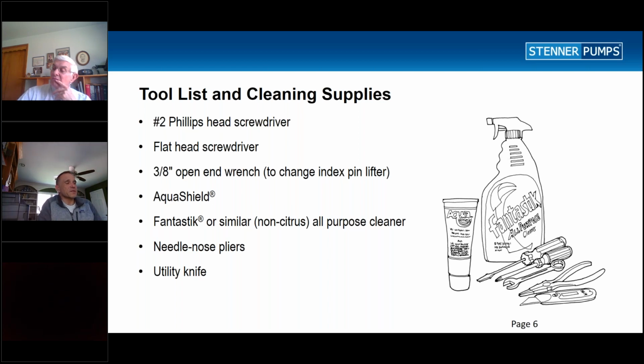One thing that I recommend is that anytime you do have a tube leak, because I see this happen often, we recommend taking all of the parts out of the head, taking the roller, shaft, take the housing off, and clean everything with some good clean water. And then also clean it with some Fantastik, and especially the rollers. One of the most likely things that happens when you have stuck rollers is when the chlorine starts getting crusty, it starts hanging the rollers up, especially after a tube leak.